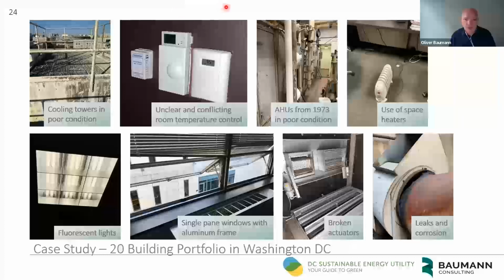The next picture shows air handling units from 1973 that were probably never cleaned or maintained since then. There's a lot of opportunity here. Understanding the condition of these systems is important for identifying the appropriate energy efficiency measure, whether it's upgrading a fan from belt-driven to direct-driven, or adding a frequency drive to a fan motor. On a system like that, I wouldn't even think about such an individual measure - I'd think more holistically and ask what we could do if we replaced the entire air handling unit.